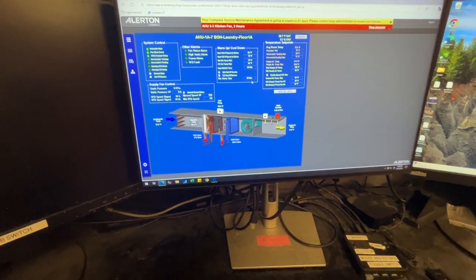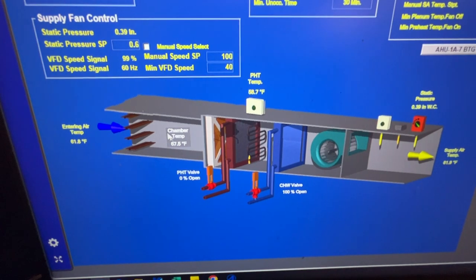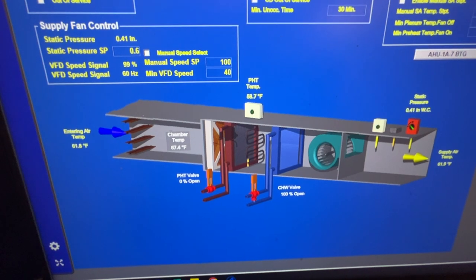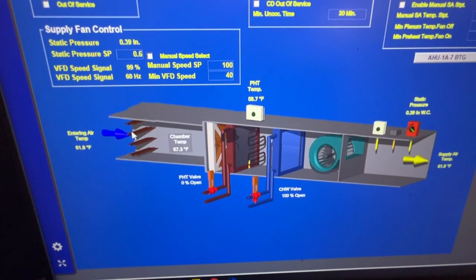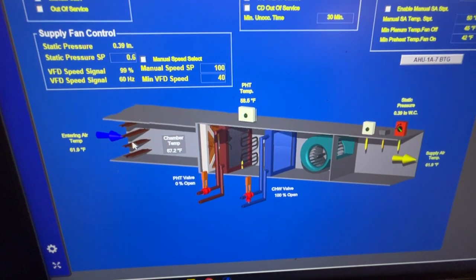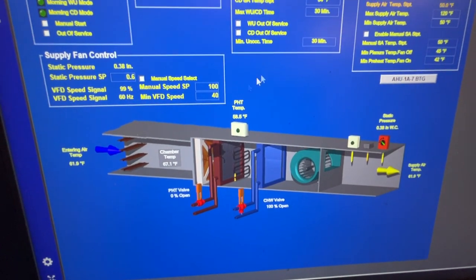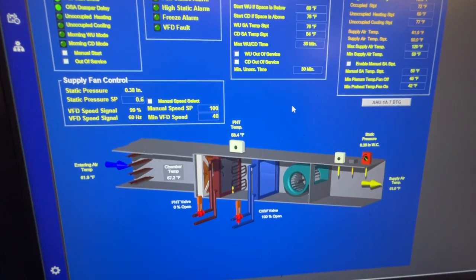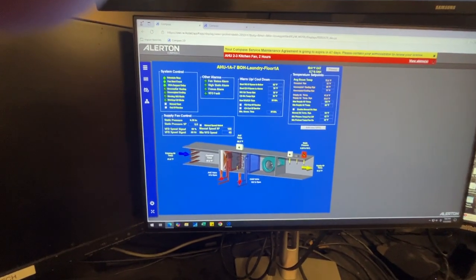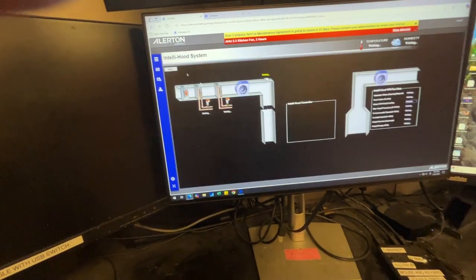When it's like 95 degrees out, the chilled water just doesn't get cold enough. It doesn't keep up. So one thing that we do is, right before the filters, there's a door in there. On days when it's really hot, if you leave that open, it just acts as a return. Rather than bringing in 94-degree air, it'll bring in air from the space at 75, and then we can cool it without it going outside. They should have put a return in there. It probably would have created pressure issues because there's not a full open air plenum back, but it's just something to know, because the laundry team complains about it when it gets really, really hot, and the only thing you can do is open that door.